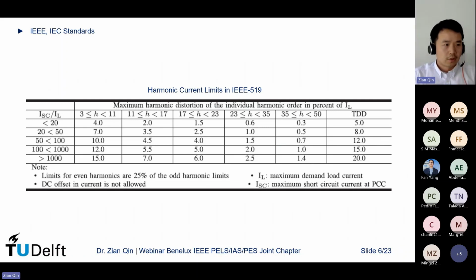So yeah, okay. As common sense, whenever talking about harmonics, you may say, okay, 5%, right? 5% THD. As long as you fulfill this, the THD is lower than 5%, it's good. But if you open the standard and look into it, you may see that the standard states much more than this 5% THD. Actually, for each frequency range, you will see a certain limit of the harmonic current. And this limit is also related to the short circuit ratio.